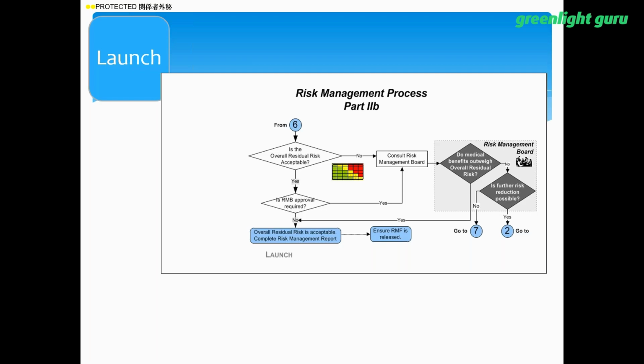At an occurrence level of 2, that would typically mean that we had experienced some level of S5 with that product. Usually that's very rare, and usually a lot of the S5s that would be identified are actually identified as hypotheticals out of that risk management. However, there may be occasion where the risk management board is examining something where you do have, for example, an S4 O3 or an S5 O2, that will be a very in-depth and very serious and lengthy discussion.